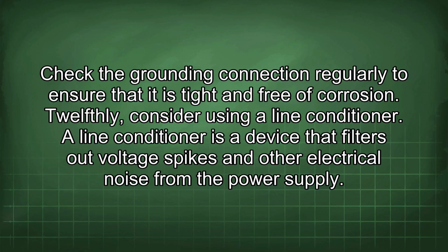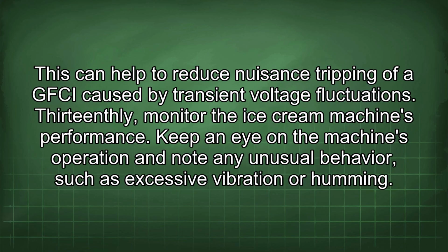12thly, consider using a line conditioner. A line conditioner is a device that filters out voltage spikes and other electrical noise from the power supply. This can help to reduce nuisance tripping of a GFCI caused by transient voltage fluctuations.